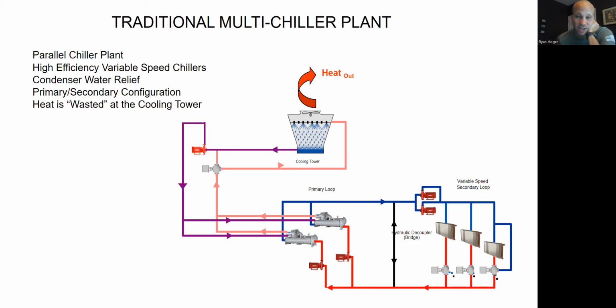The condenser water side on the left over here, that's a separate water loop. So the water in these pink and purple pipes never touches the water in these red and blue pipes. It's totally separate. Inside the chiller is my refrigeration cycle that we talked about in module 1: evaporator, condenser, compressor, expansion device. But instead of being like your house where I have a condenser coil outside and evaporator coil inside, and those guys just switch jobs, now I have a water-based condenser coil in the chiller and a water-based evaporator coil in the chiller. So there's two heat exchangers. One is water to refrigerant, and the other one's refrigerant to water.